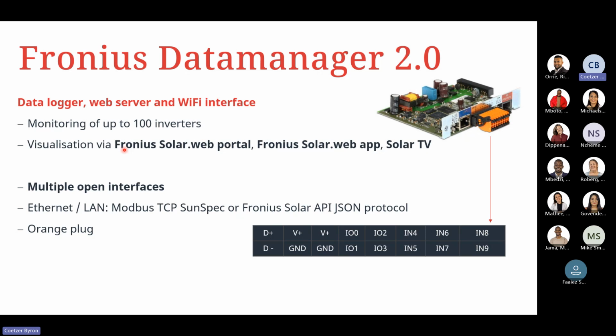Again, it is a visualization card that allows us to do this through the SolarWeb Portal, as well as using the SolarWeb apps, and lastly, the Solar TV. Again, you have multiple open interfaces. So again, using your Ethernet or LAN port for Modbus TCP SunSpec, or your Solar API JSON protocols. And again, the orange plug is for your communication of RTU or RS-485. So you'll have D plus, D negative for your smart meters, for example, and V plus and ground, and your IO ports respectively for your RS-485 connection block.